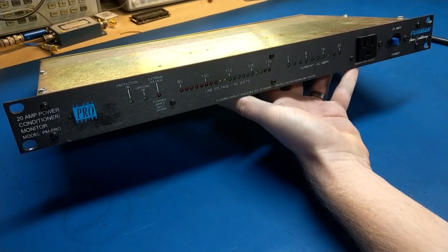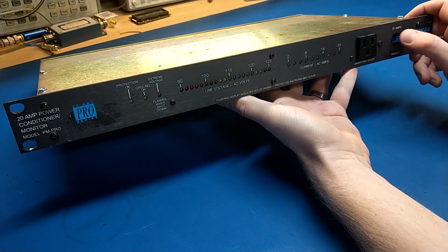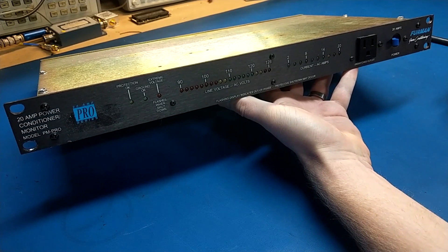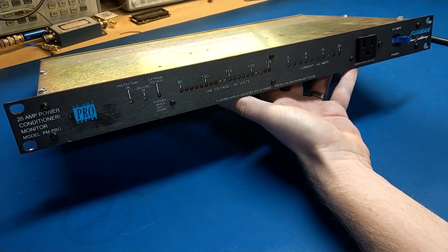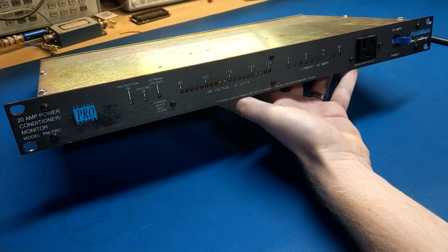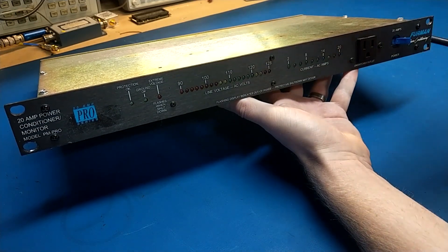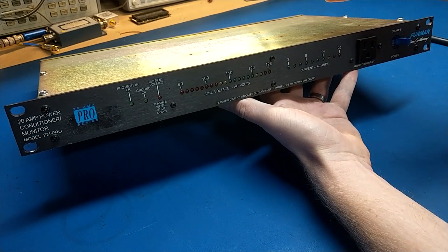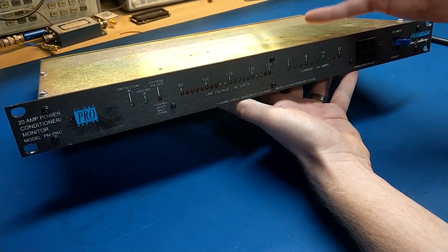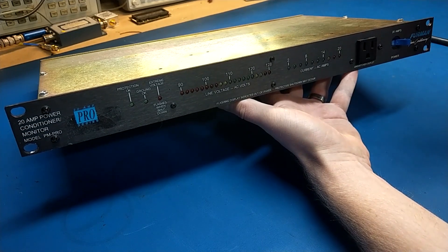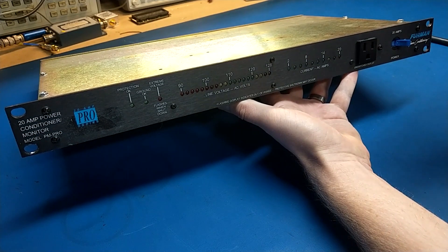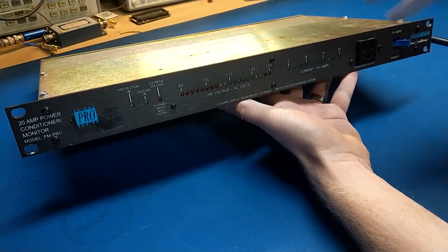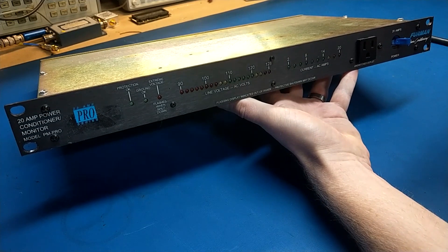So these devices basically do three things. Number one, they are basically overload protection, that's your circuit breaker on the front. Some of these are fused, I don't think this one is because it has the breaker right there. Number two, they do surge protection. So your surge protection will consist of multiple things. Typically they'll just be your MOVs, your metal oxide varistors. Beyond that they might have some spark gaps, if there's any circuit boards in there they might have some gas discharge tubes, they might have some TVS diodes. Just depending on the amount of money put in there and what they do, you may find a combination or all of those.